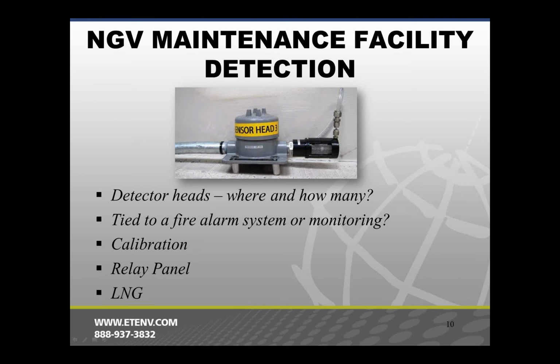But you need to check them. Usually it's 2 times a year with some test gas and make sure that your calibration is correct and zeroed properly. One other aspect that comes in with the gas detection is, detection is one thing, and then you need to tell the rest of the building systems what to do.